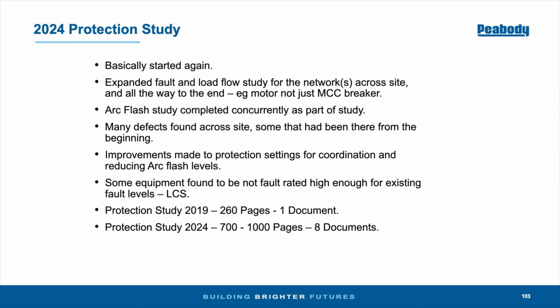So we went through that process, and now we're basically auditing what we've got back, and fixing that up as we go. We actually found some equipment where the fault levels weren't rated high enough for where they were actually in use. So some LCSs weren't rated, their fault levels weren't rated high enough.